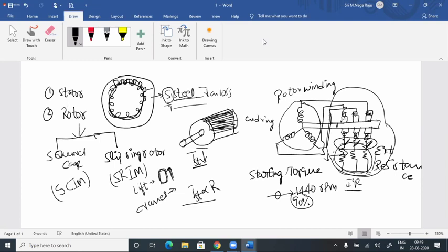Like traction also. Traction means trains, locomotive engines. In traction also, the train starts when all the passengers have filled the compartments. Initially the load is more. When the train is moving, the torque required will be less. So in traction also we use slip ring induction motors. In olden days in traction, we used DC series motors. We know a DC series motor also has high starting torque.